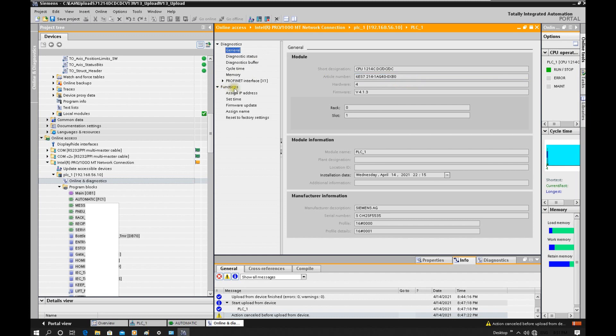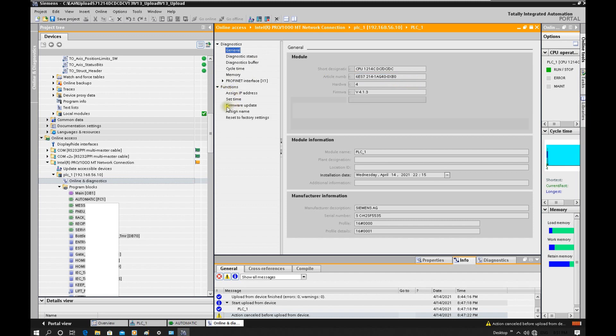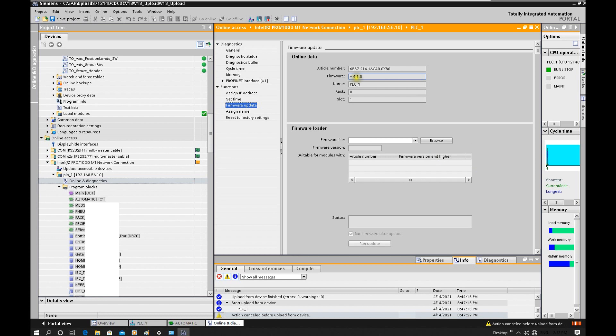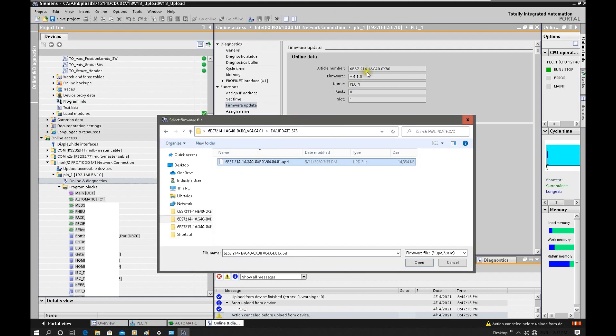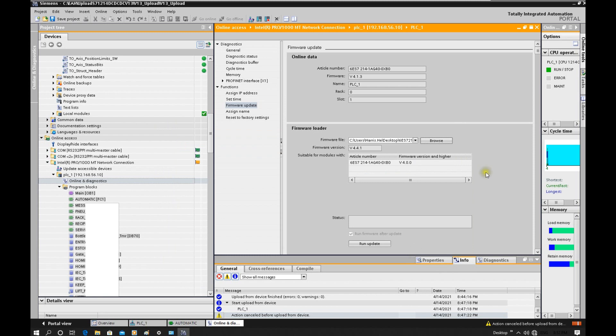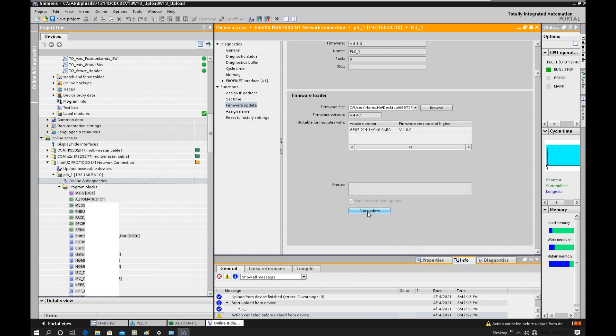Browse the functions and go to firmware update. The current version is 4.1. From here let's browse for the firmware file. I will browse to 1214-1AG40. Double-click it. You must double-check that the article number matches — 1AG40. Click open, and then let's click Run update.